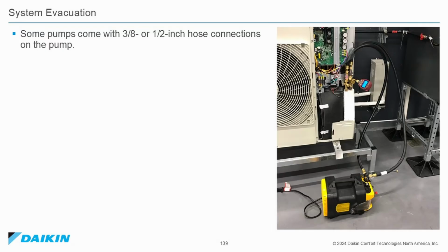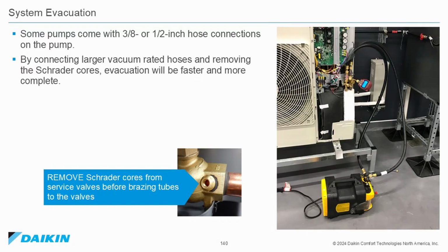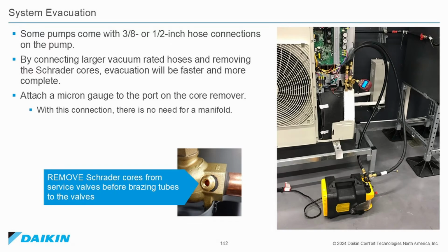System evacuation. Some pumps come with 3/8 or 1/2 inch hose connections on the pump. By connecting larger vacuum-rated hoses and removing the Schrader cores, evacuation will be faster and more complete. Attach a micron gauge at the port of the core remover. With this connection, there is no need for a manifold.